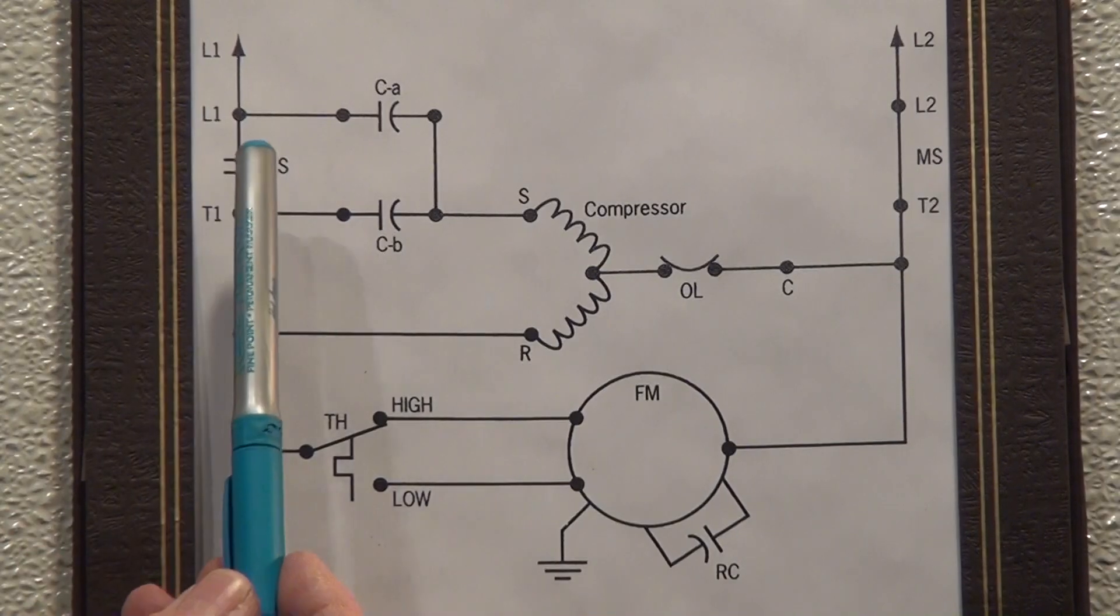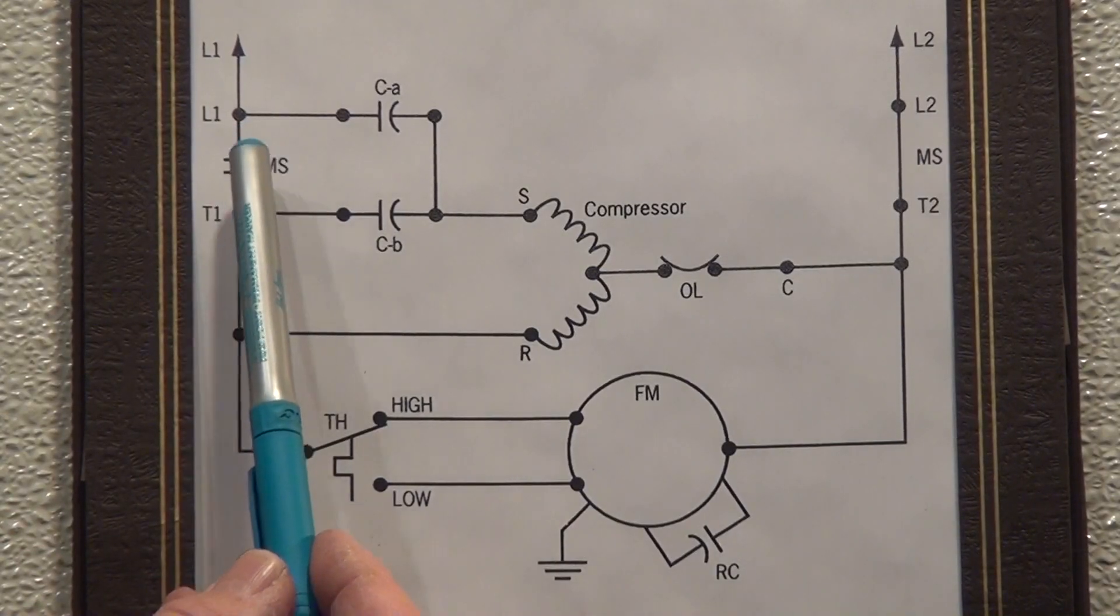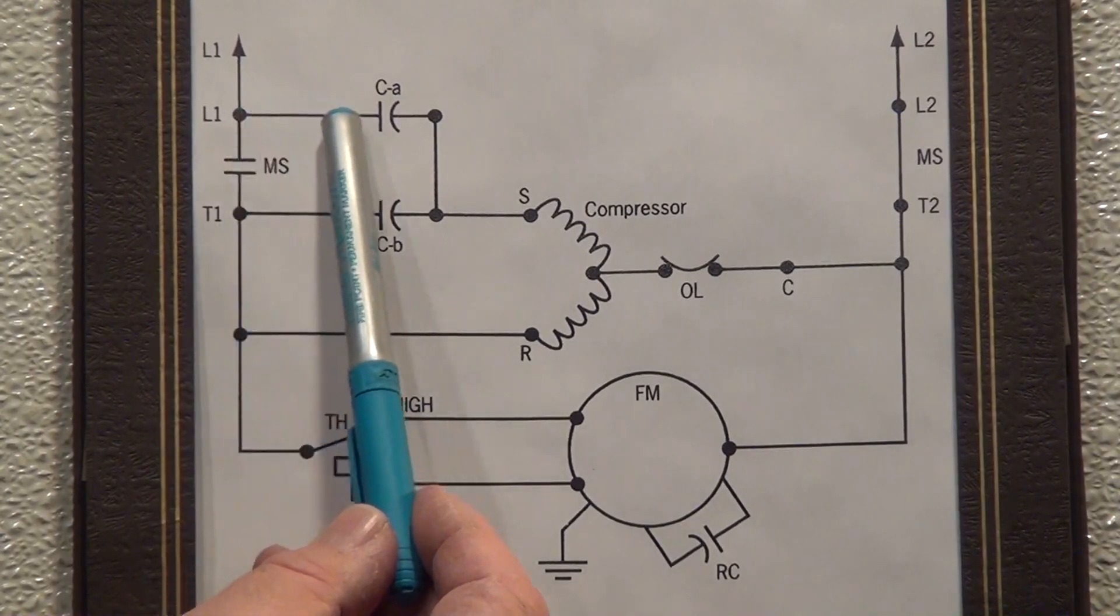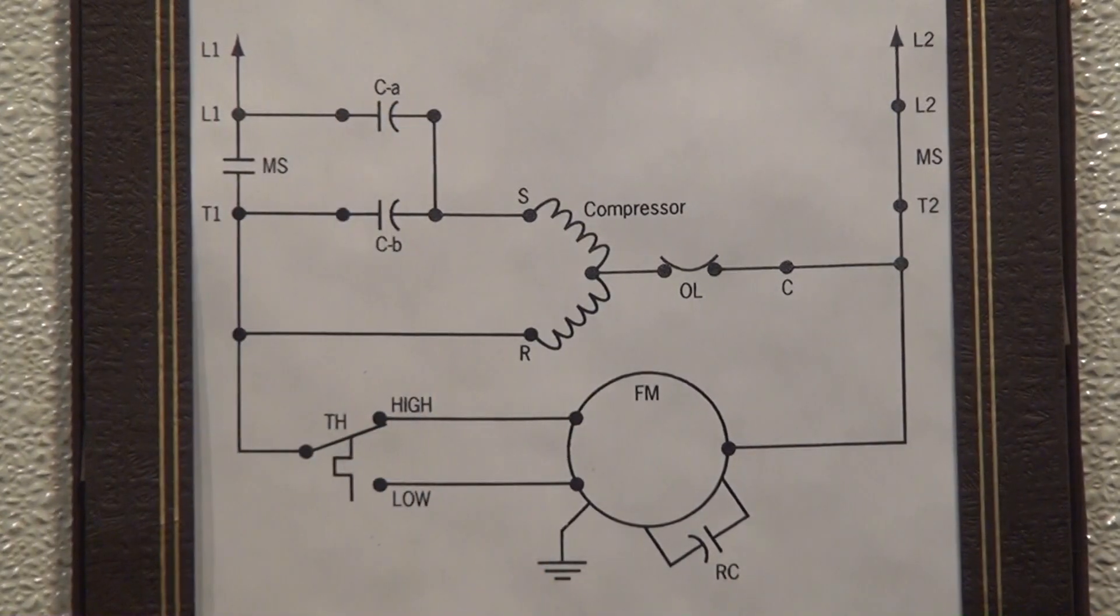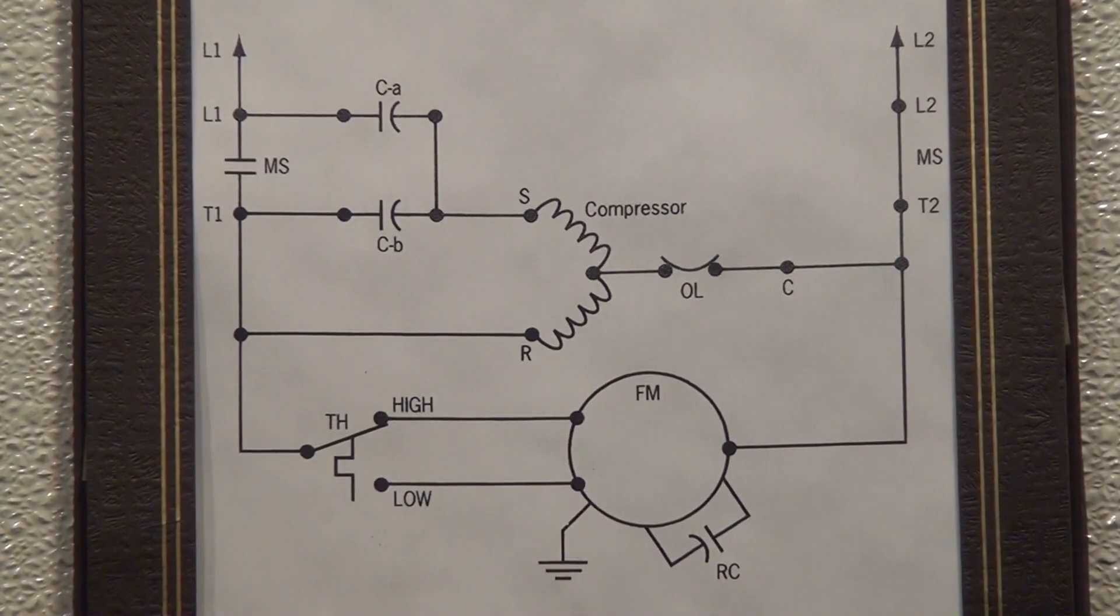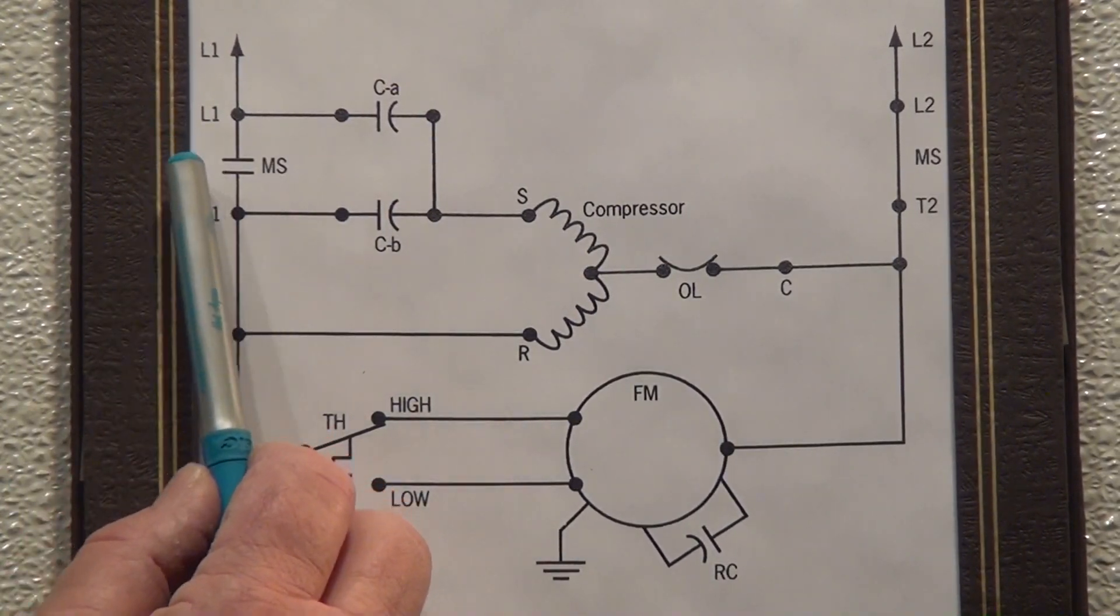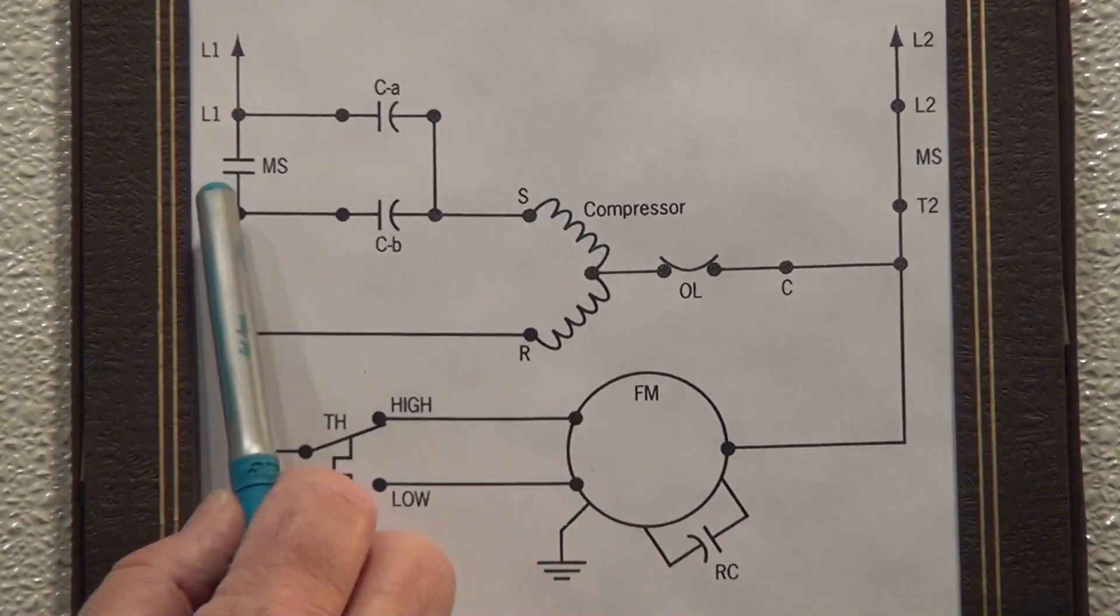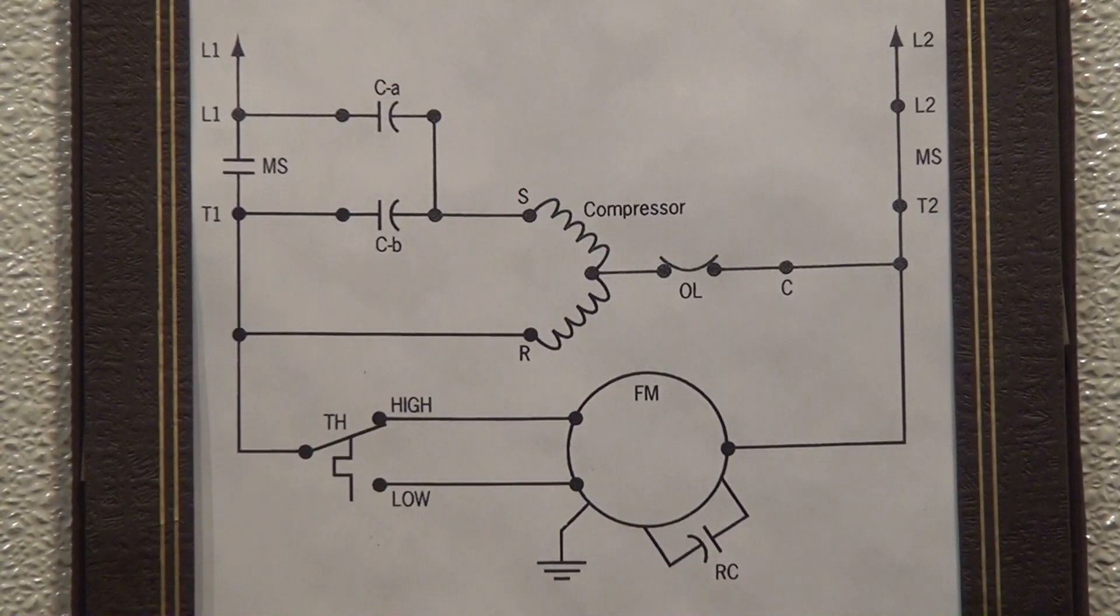The other point I want you to understand is that this particular piece of equipment employs two capacitors in its original format. One is labeled CA, in other words capacitor A, the other one is labeled CB which is capacitor number two. And you're going to notice that both of these capacitors are wired in series with the start winding. That's a point that we want to make there.